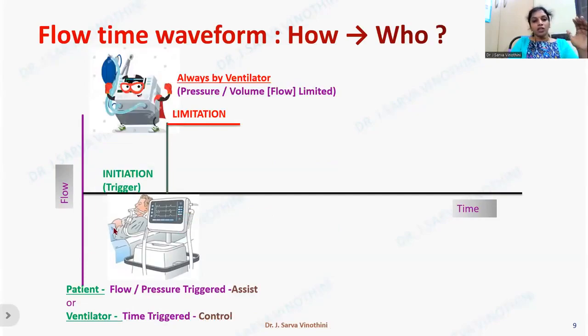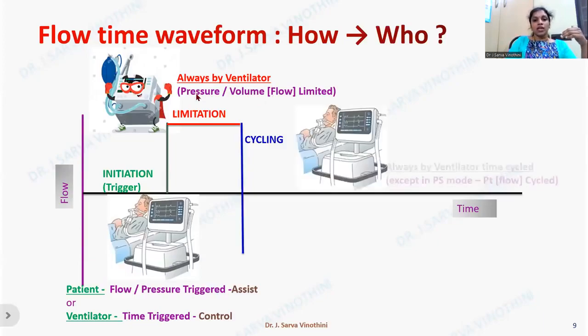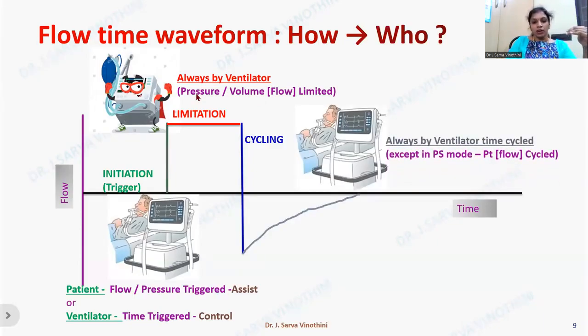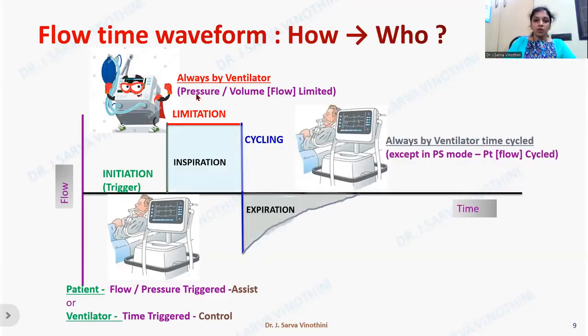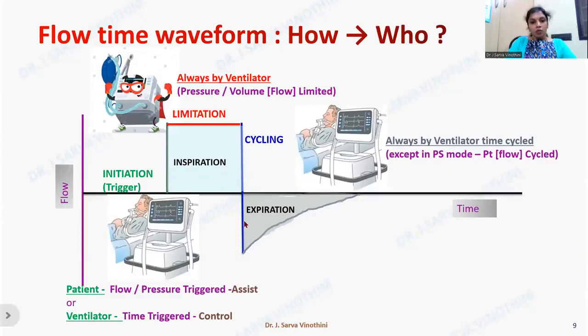The limitation of the breath is always done by the ventilator, and it can be either pressure or flow. If pressure-limited, we call it a pressure-limited breath; if volume or flow-limited, we call it volume-controlled ventilation or pressure-controlled ventilation. Cycling is almost always done by the ventilator, except in pressure support mode where it is done by the patient via flow cycling. So the initiation, limitation, and cycling together lead to inspiration and expiration — giving us the inspiratory and expiratory waveforms in the flow-time scalar.